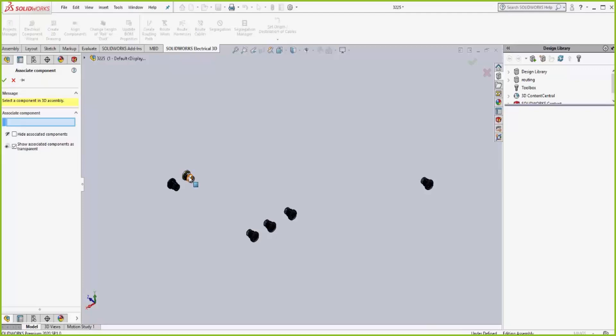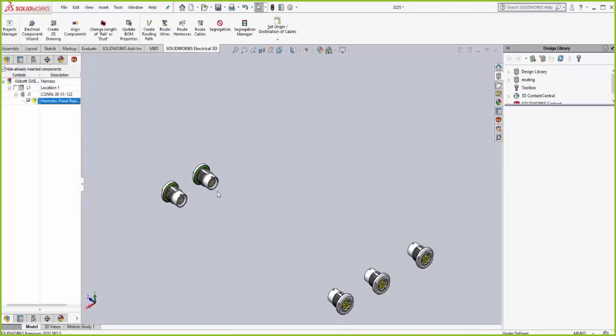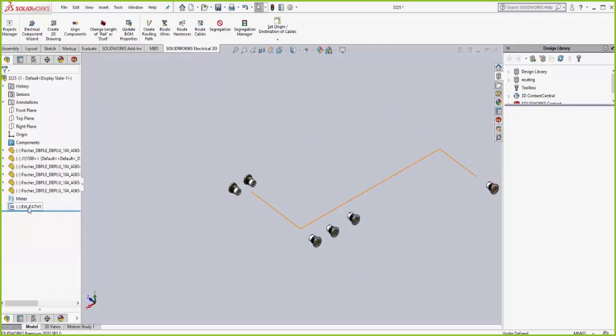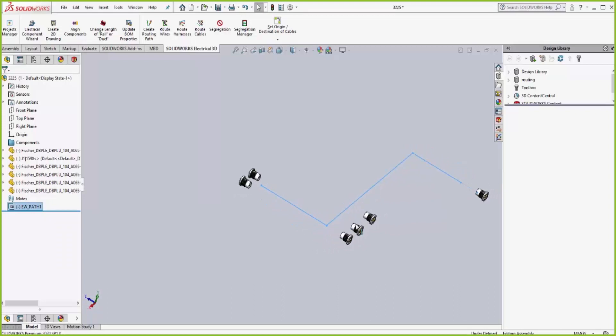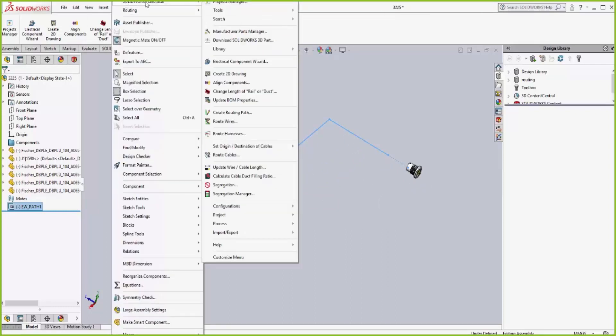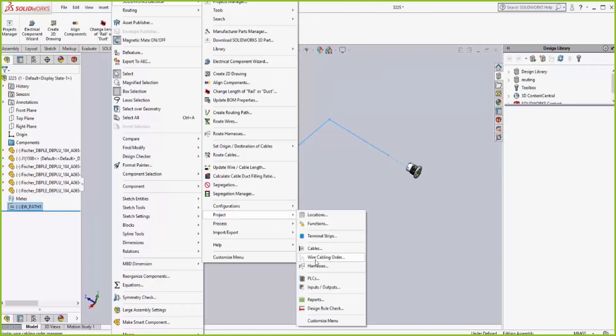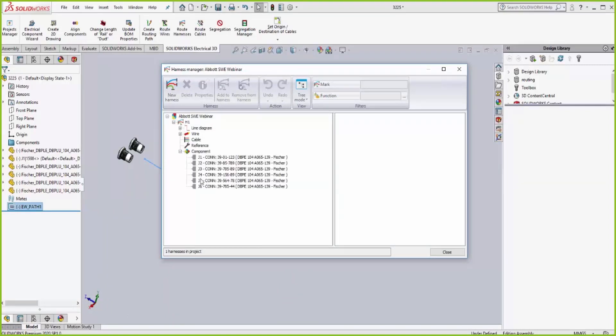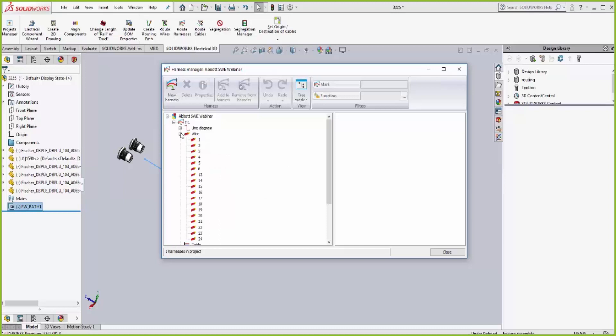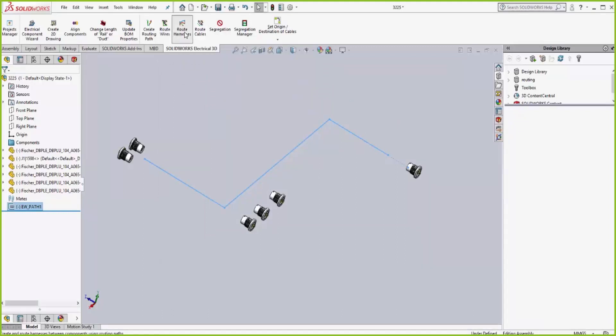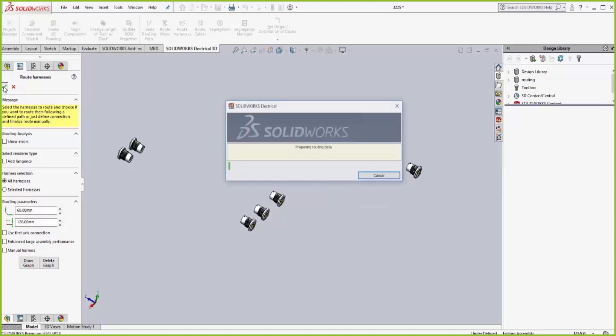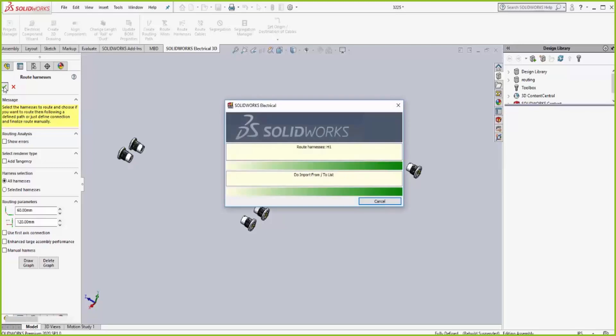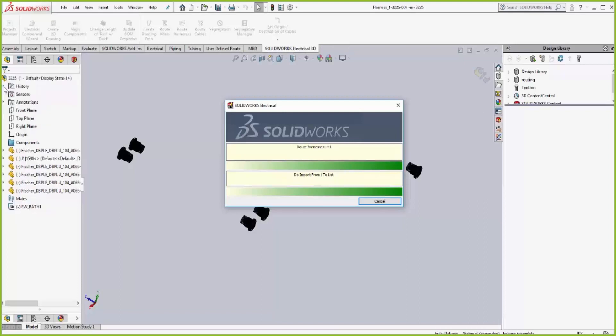We're going to look at this fact that in this case we've got these connectors that mechanical has placed, but again that associativity is still required. For this one connector that has not been associated yet, we'll pick that 3D model and go ahead and associate it. This is figuring out that J1 is required and part of this harness. Again, we've got another sketch which is telling us where we want this route. It's not in open space, but you could use contoured surfaces and then offset those surfaces to be able to give you some lines for being able to follow on a path. This harness itself has many pieces to it—it has six connectors, but it also has a number of wires with each of those wires going to a specific point and landing.